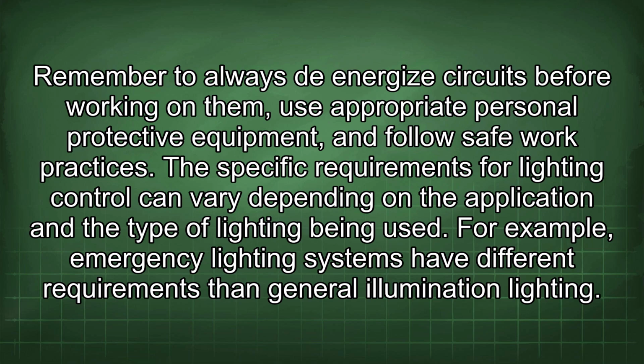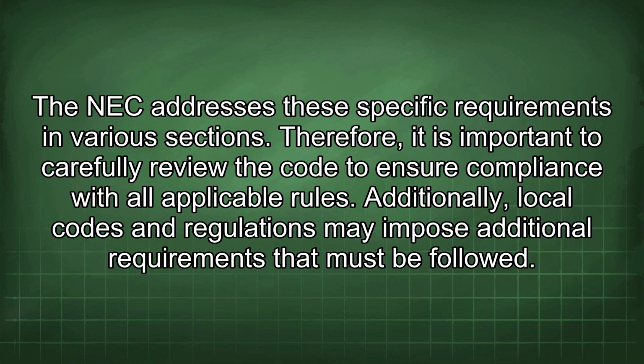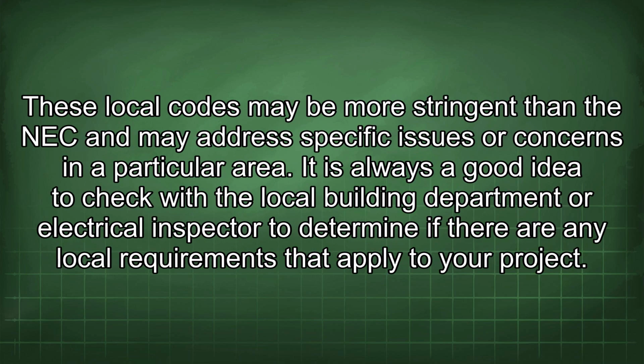The specific requirements for lighting control can vary depending on the application and the type of lighting being used. For example, emergency lighting systems have different requirements than general illumination lighting. The NEC addresses these specific requirements in various sections. Therefore, it is important to carefully review the code to ensure compliance with all applicable rules. Additionally, local codes and regulations may impose additional requirements that must be followed. These local codes may be more stringent than the NEC and may address specific issues or concerns in a particular area. It is always a good idea to check with the local building department or electrical inspector to determine if there are any local requirements that apply to your project.